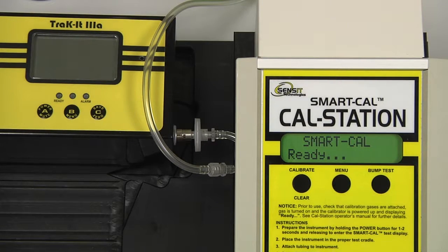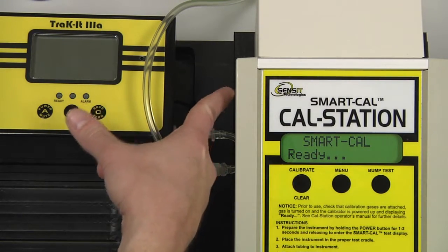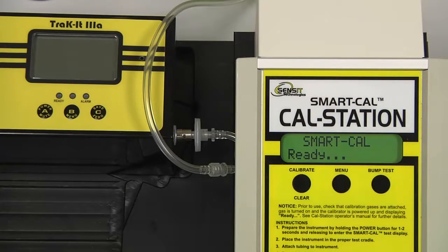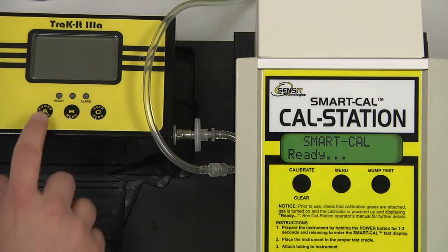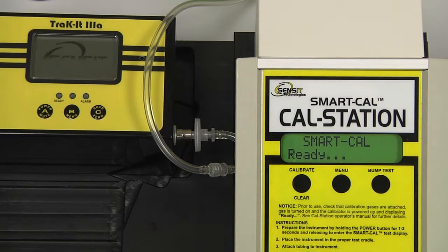To begin, ensure that the cal station is powered on and is displaying SMART-CAL ready. Attach the instrument hose and adapter to the TRAK-IT IIIa, ensuring that it is not blocking the optical path between the instrument and the cal station. And power on the instrument by pressing and holding the A button until the SENSIT logo appears. Allow the instrument to go through the full warm-up cycle and arrive at the working display.